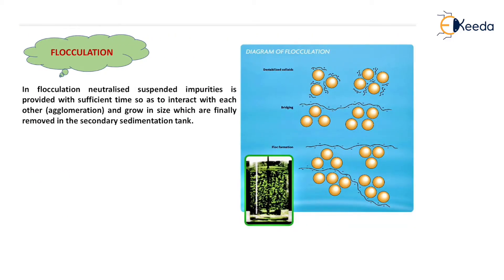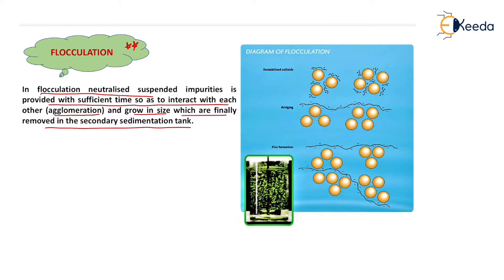The next process is flocculation. When we add the coagulant and after providing rapid mixing, we need to provide slow mixing for floc formation. In flocculation, neutralized suspended impurity is provided with sufficient time so as to interact with each other — that is known as agglomeration — and grow in size, which are finally removed in the secondary sedimentation tank. We need to provide slow mixing to give sufficient time for all the particles to interact, and when they grow in size, they are removed in the secondary sedimentation tank as flocs.